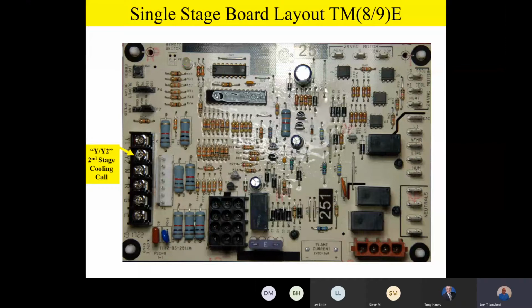Now you're also going to notice, Tame, that when we talk about two-stage terminals like this, it's very common for our champion engineers to have silk screened or labeled on the control boards Y/Y2. Now the reason they do that is this. Y1 is first stage cooling airspeed, which is going to be 65% of your total cooling airflow. You're going to have to set that up for 65%. Y/Y2 is your second stage airflow. But now hang on a second.